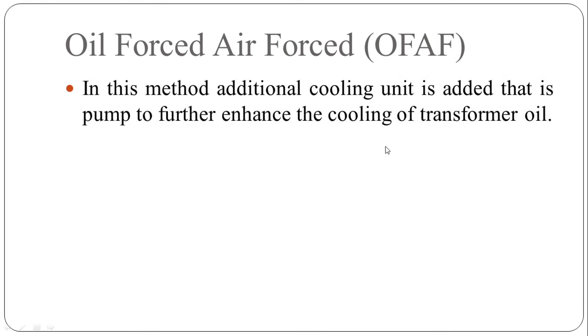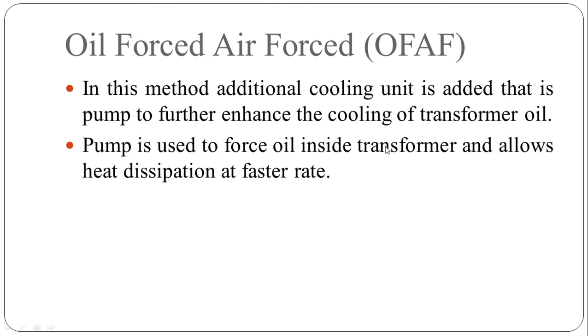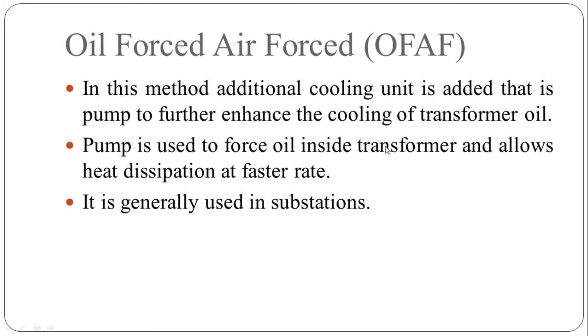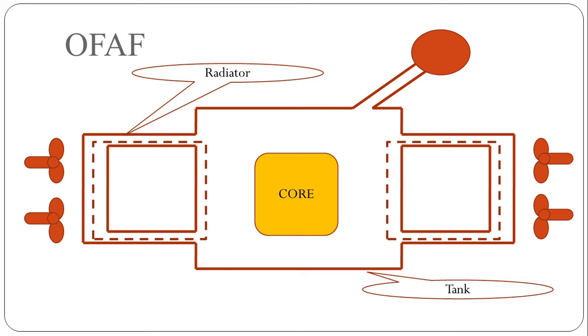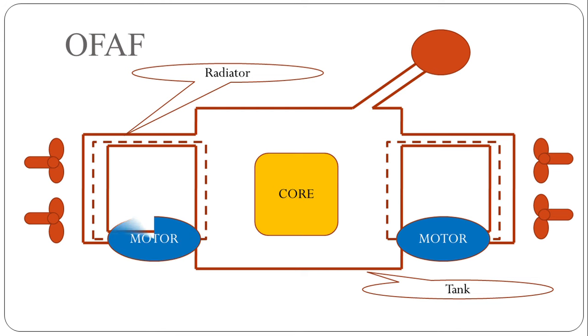The third method is oil forced air forced (OFAF) cooling. In this method, an additional cooling unit — a pump — is added to further enhance cooling. The pump forces oil inside the transformer, allowing heat dissipation at a faster rate. It is generally used in substations. Here you can see: starting from ONAN, adding fans gives ONAF, and adding motors for circulation of oil gives oil forced air forced cooling. The motors force the oil and fans force the air — that is why it is called the OFAF scheme.